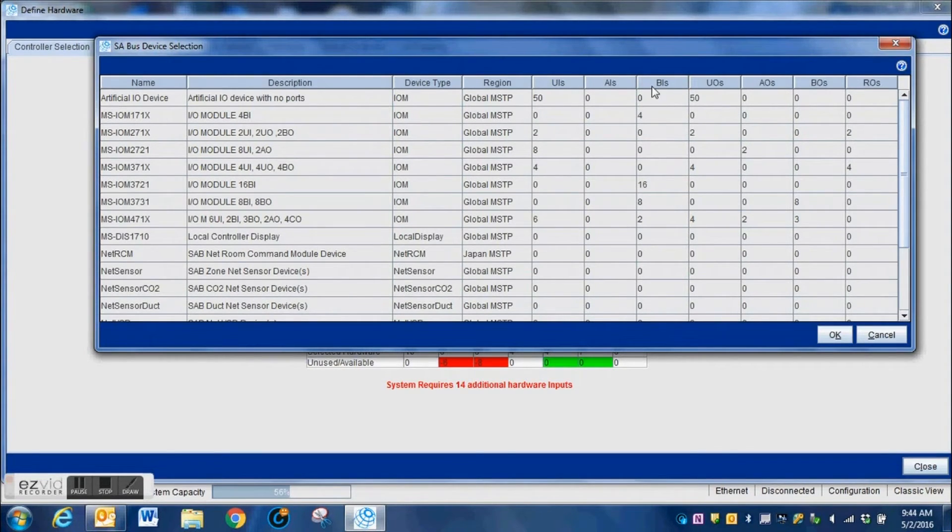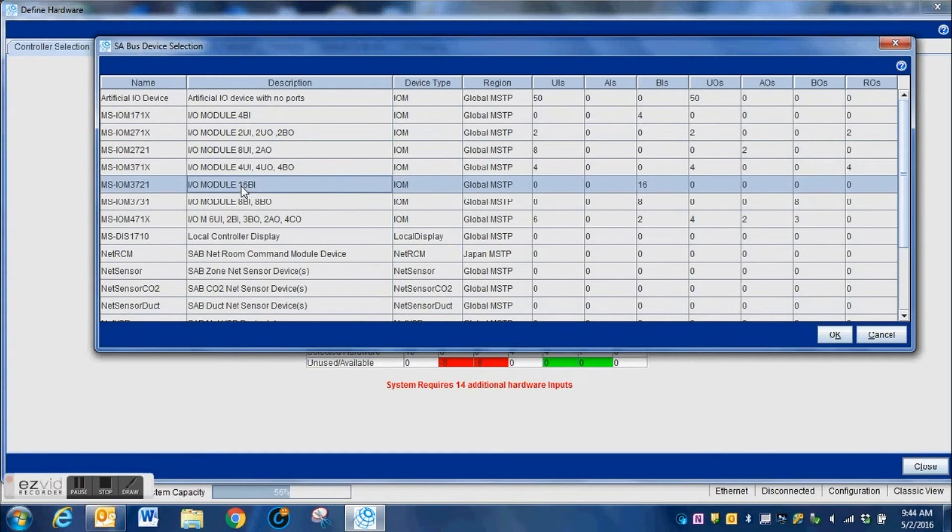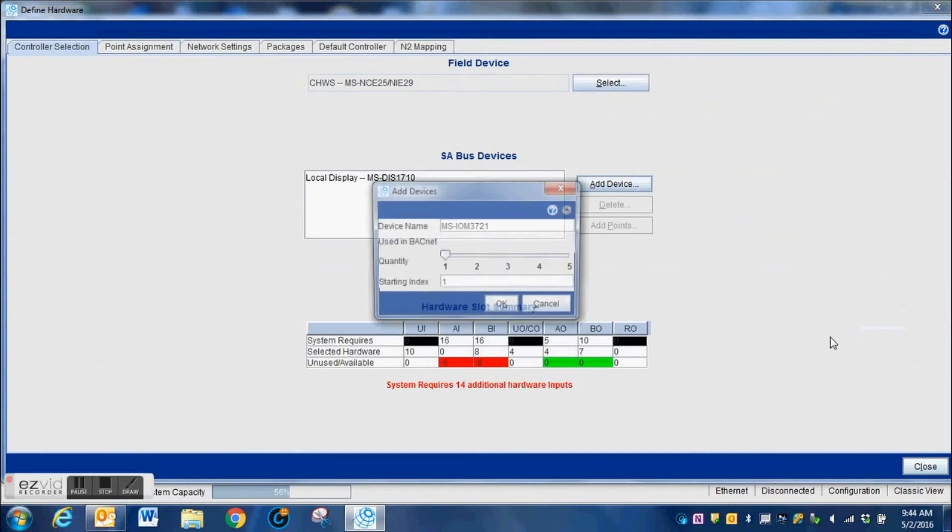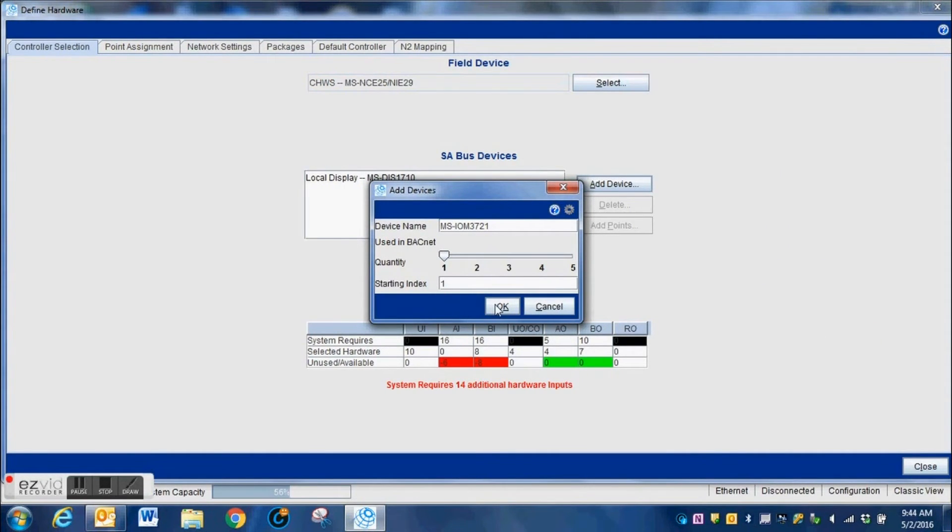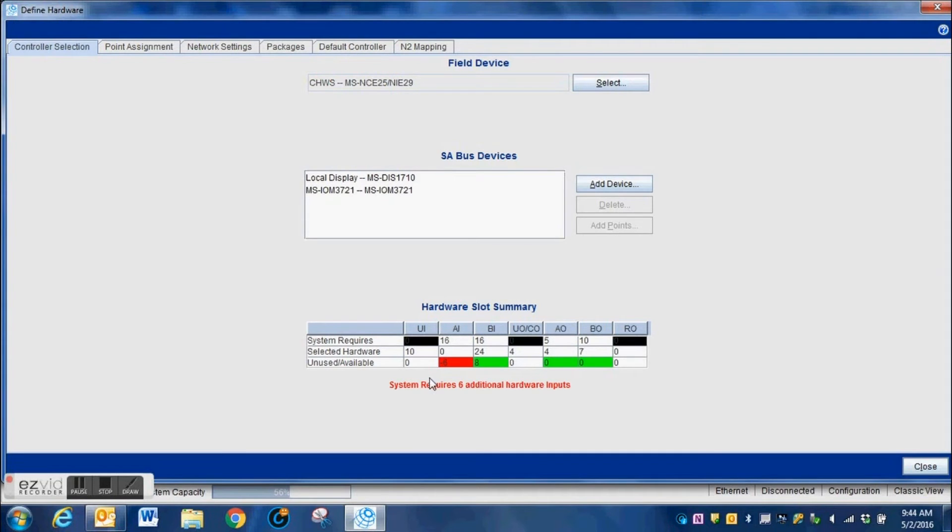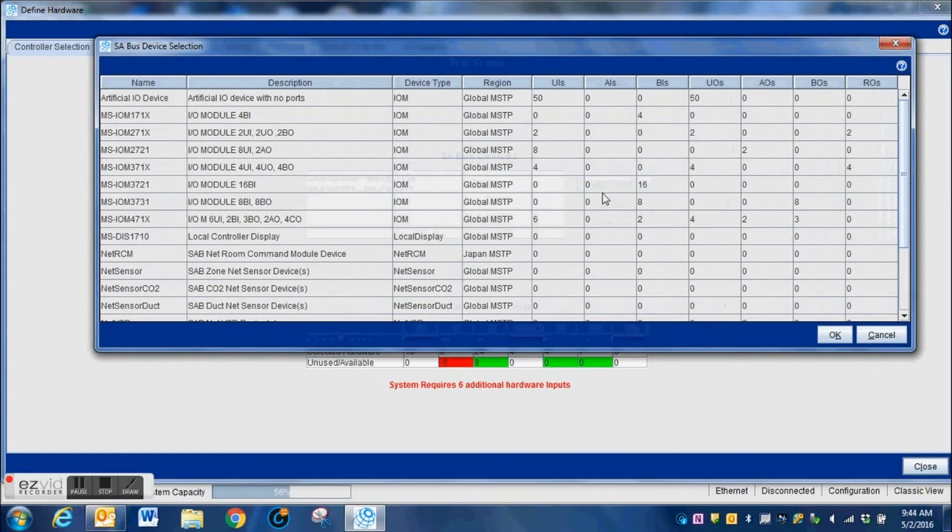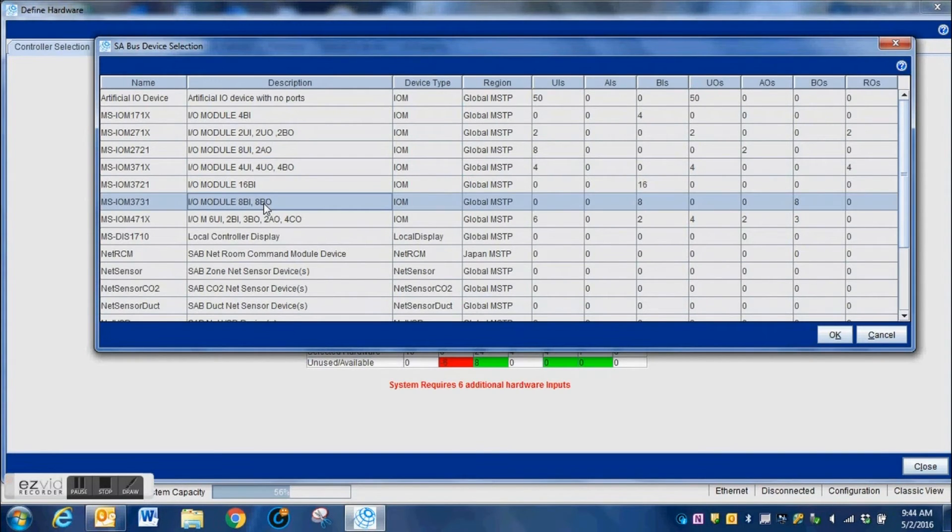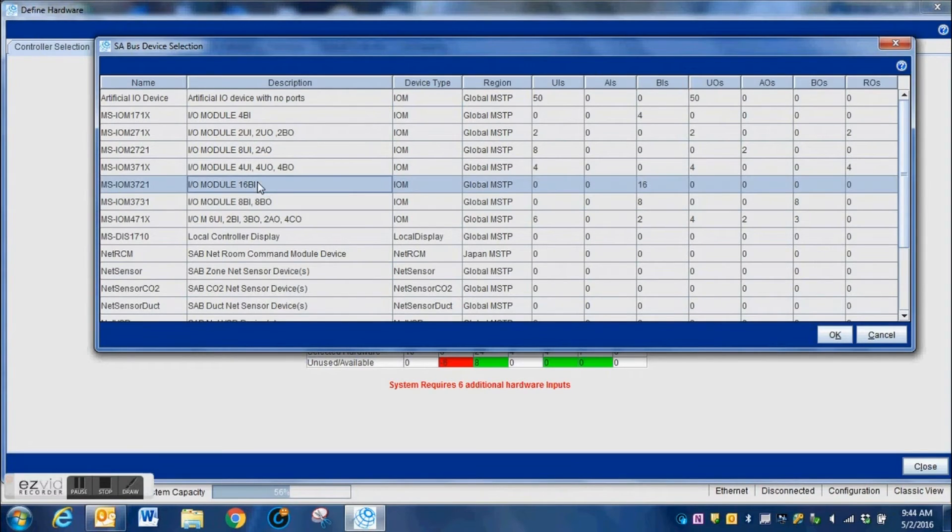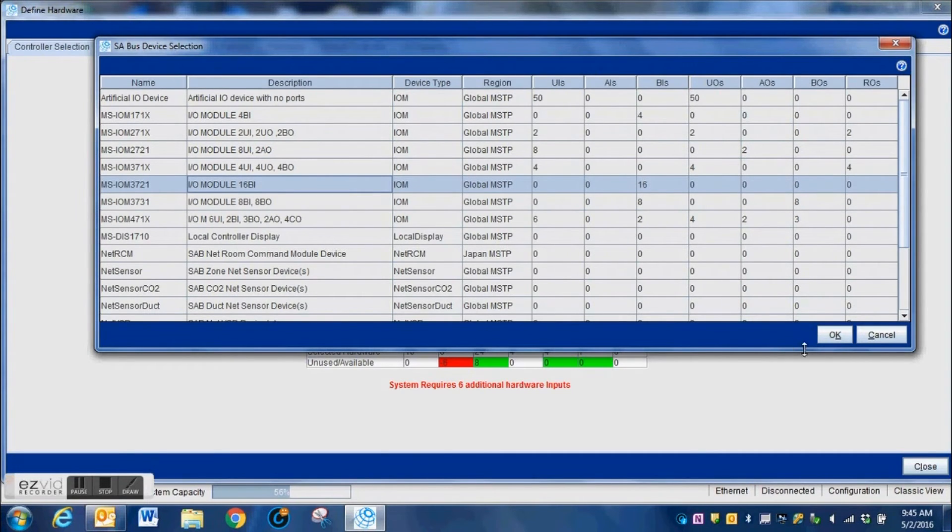You cannot start a pump if you don't have a binary output. You cannot turn on the chiller if you do not have the appropriate output for it, for a run relay. You can't control a drive or anything like that if you do not have the correct number of hardware inputs and outputs. Here we're going to grab one of the IOMs with this particular model.